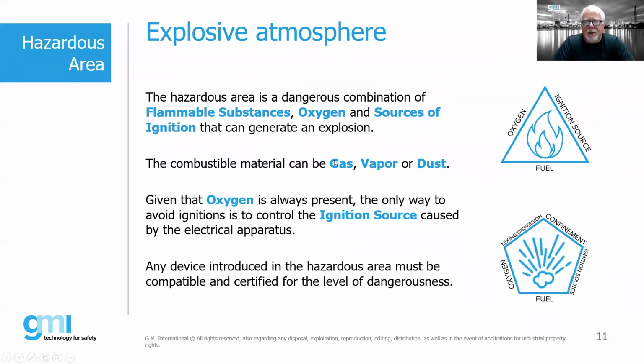So what is a hazardous area? It's a combination of flammable substances, in this case gases, a combination of oxygen and a source of ignition that can create an explosion. And that material can be a gas, vapor, or dust. Typically refineries or offshore oil platforms are gas hazards, vapors. Dust might be grain elevators, those types of applications.